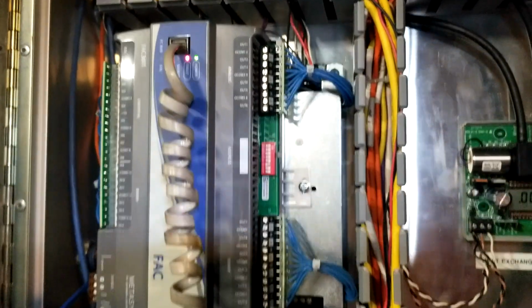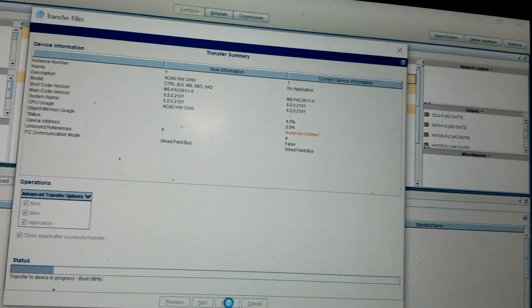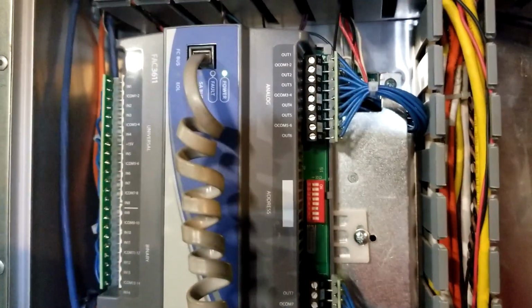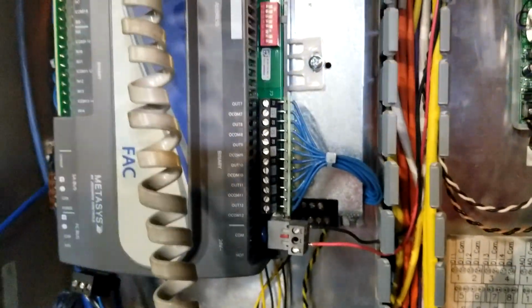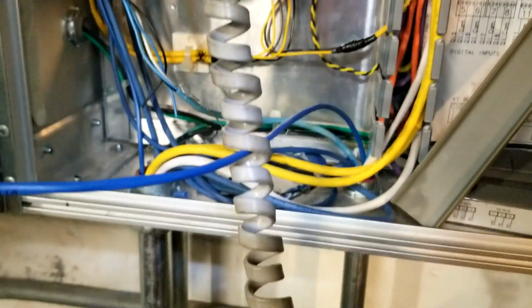Now that we've got our first controller installed, I've got my Bluetooth adapter connected to it and we're downloading the program. With this device, I'm loading both the boot and the main code, just for good measure. Sometimes if you get a controller at a different rev than what version of CCT you're using, it's required — but I have a tendency of doing it anyway. If it's a new device, I'll go ahead and download the code as well as the program. Once we get everything loaded, we'll get the system online.